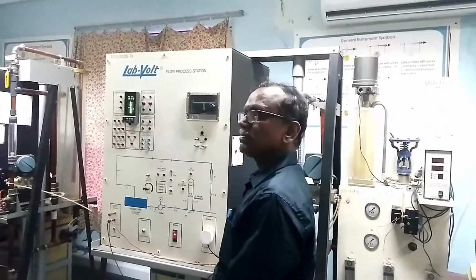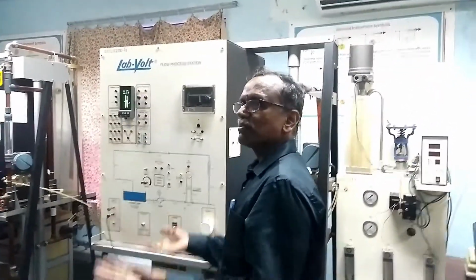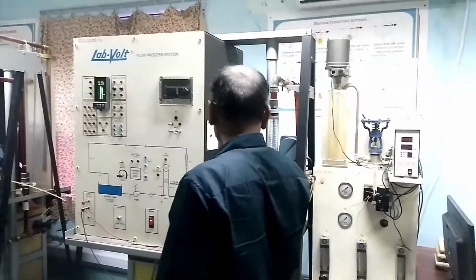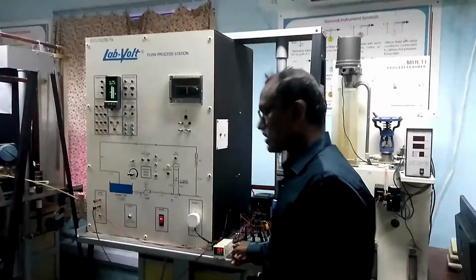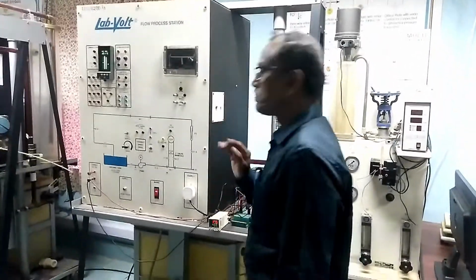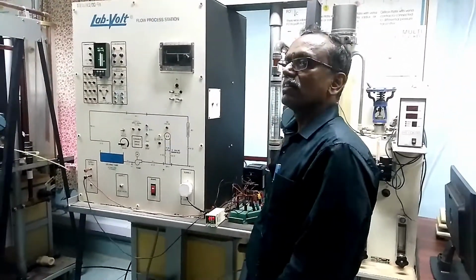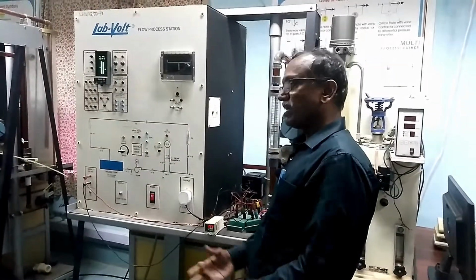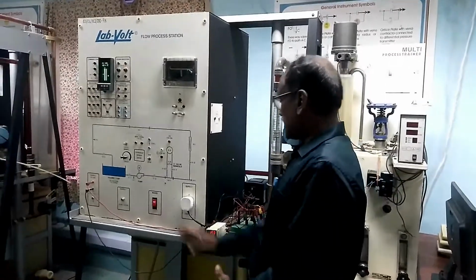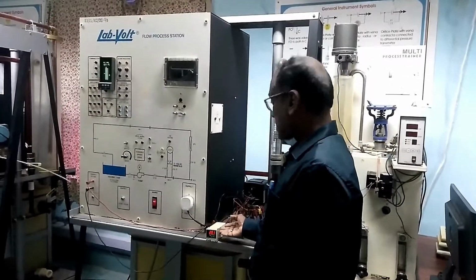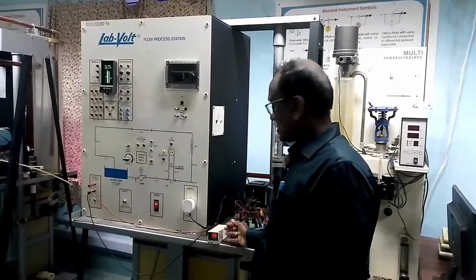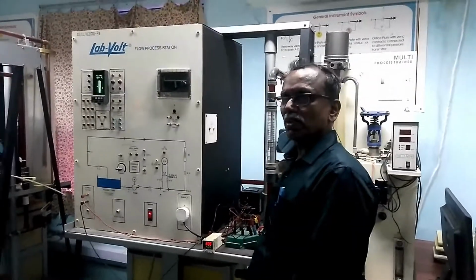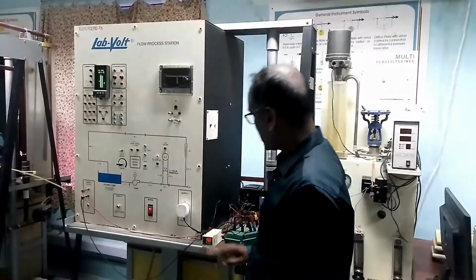1 to 5 volt. For 4 milliamps it is 1 volt, for 20 milliamps it is 5 volt. Its voltage varies from 1 to 5 volt. So we configure this PID controller in such a way that the process variable, the variable to be controlled, that is flow rate, is given as 1 to 5 volt.